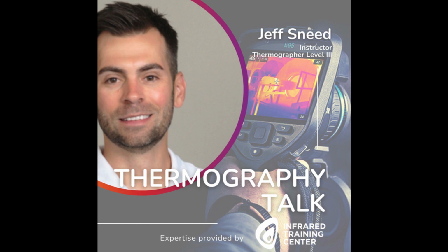Now, let's talk about some of the PPE differences that you may potentially see. Again, it's very cabinet dependent. It could be different from one cabinet to the next. All it has to do with is the incident energy that's in the panel. So you should look at the incident energy, which would be the task 1 that we went over, and then you should also correlate that with task number 4, the PPE that's required. You need to tie the two systems together. Yes, you should wear the PPE, but that PPE should have the number that's above task 1, just as a review. A large benefit to using thermal imaging, thermography, is we can be well outside of these working distances.